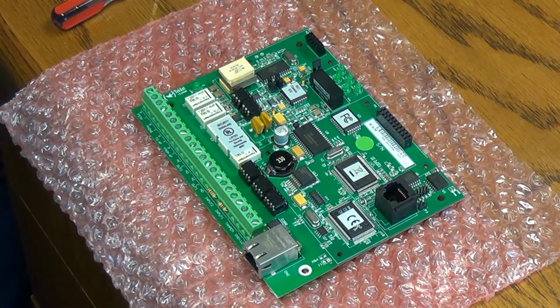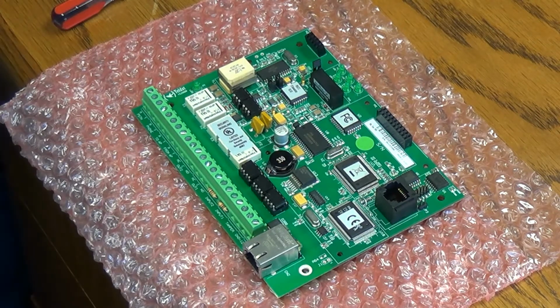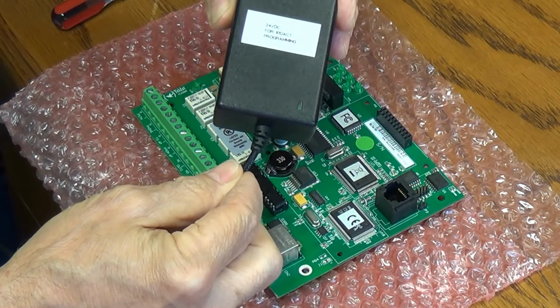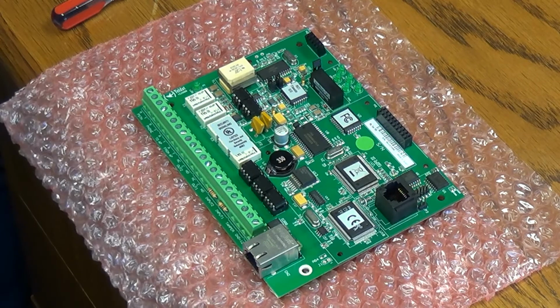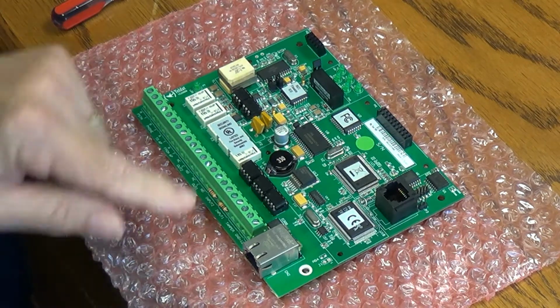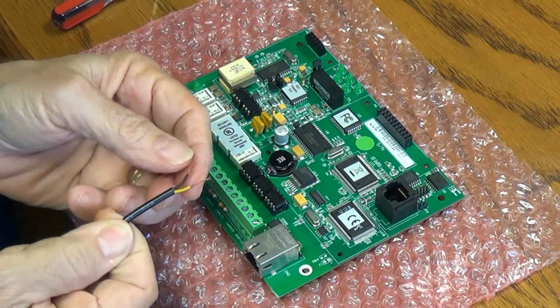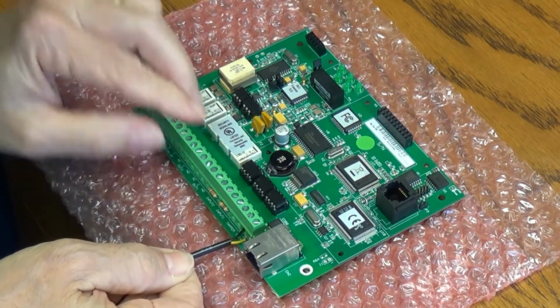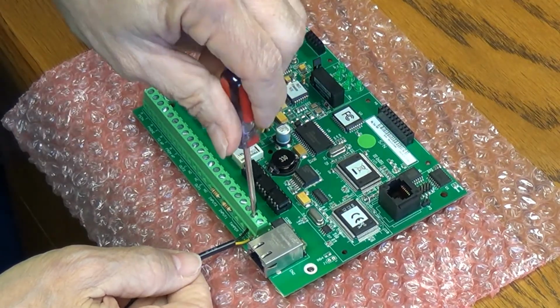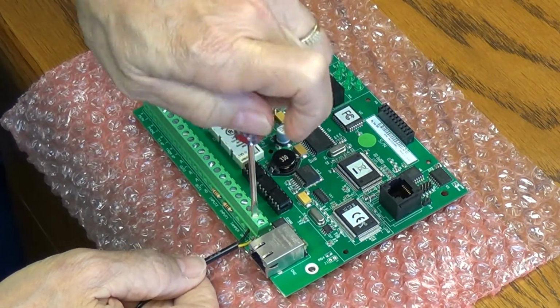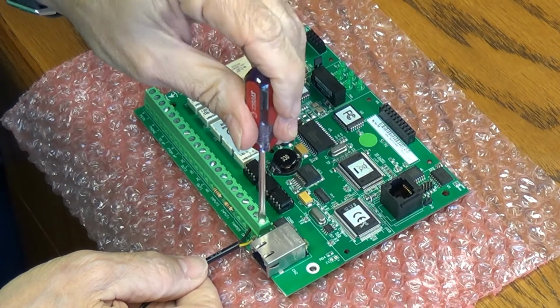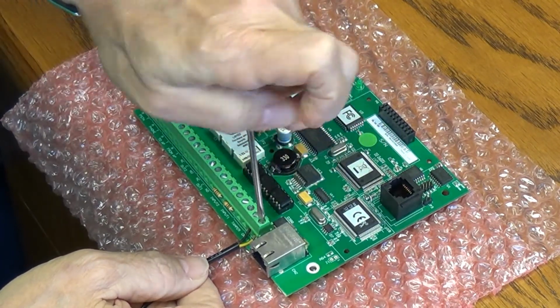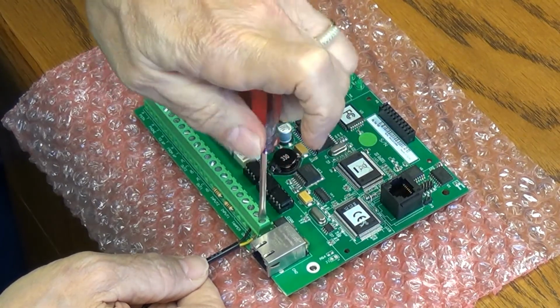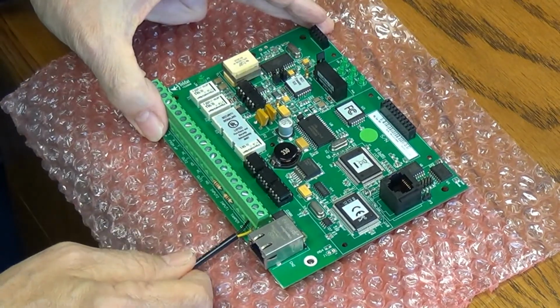I'm going to be going over how to program the IPDACT card. First of all, you need a 24 volt or 12 volt DC power supply. This card will take either voltage and you don't have to set any jumpers for it. The first lead is the hot lead, the second lead is the ground lead. I'm going to go ahead and tighten those down by turning clockwise with the standard screwdriver. Just like that, they're nice and tight.